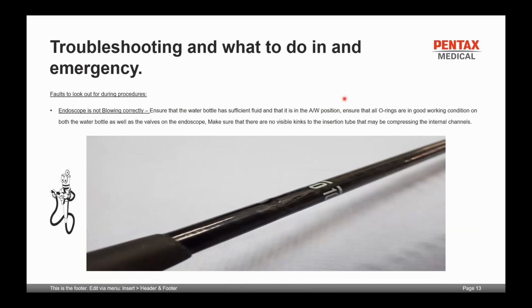Another thing to look at is your O-rings on the endoscope, and not only the O-rings on the valves, but on the water bottle as well. The water bottle has about 3 O-rings on the bottle that you need to look at, and then obviously the valve O-rings. Very important to look at both sets of valves, the air, water, and suction valve, because sometimes the endoscopist will say that the endoscope is not insufflating. During a colonoscopy, it's required to inflate the bowel to be able to advance the endoscope.